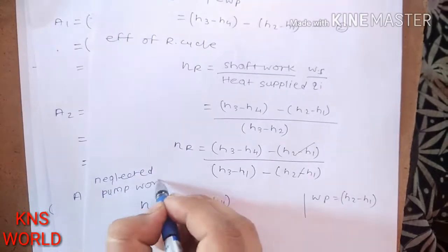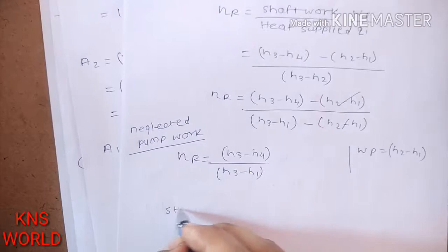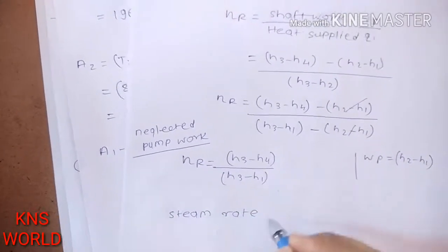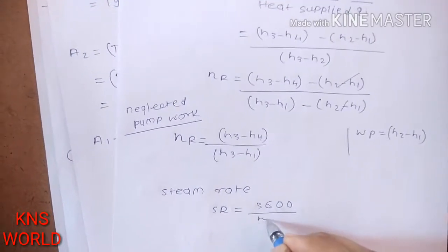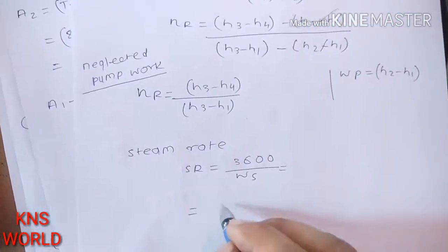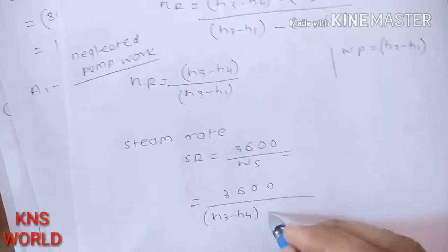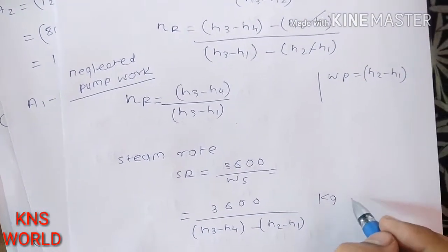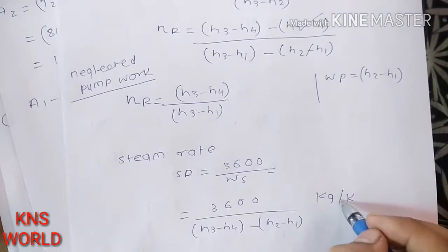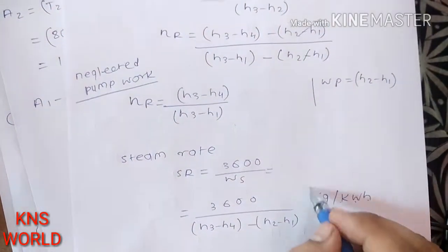Finally, the steam rate is found by: Steam Rate = 3600 / WS = 3600 / [(H3 minus H4) minus (H2 minus H1)]. The unit of steam rate is kg per kilowatt-hour.